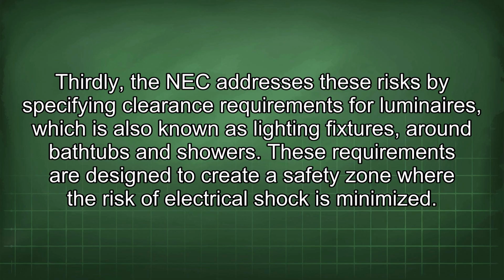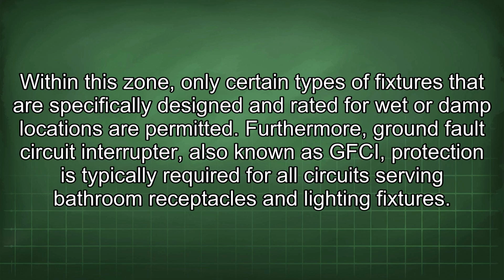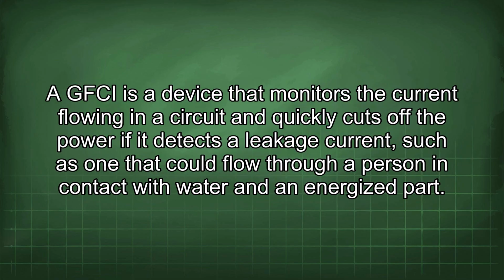Thirdly, the NEC addresses these risks by specifying clearance requirements for luminaires, which is also known as lighting fixtures, around bathtubs and showers. These requirements are designed to create a safety zone where the risk of electrical shock is minimized. Within this zone, only certain types of fixtures that are specifically designed and rated for wet or damp locations are permitted. Furthermore, ground fault circuit interrupter, also known as GFCI, protection is typically required for all circuits serving bathroom receptacles and lighting fixtures. A GFCI is a device that monitors the current flowing in a circuit and quickly cuts off the power if it detects a leakage current, such as one that could flow through a person in contact with water and an energized part.